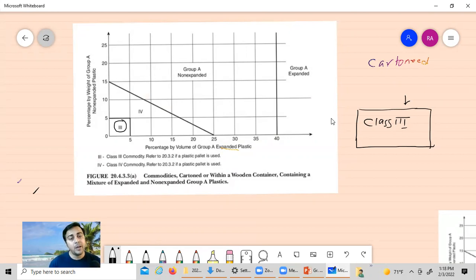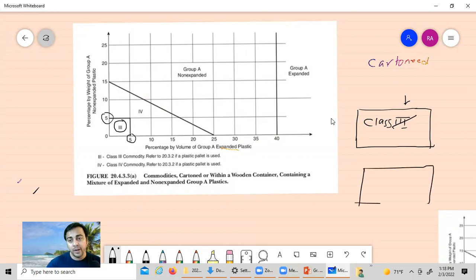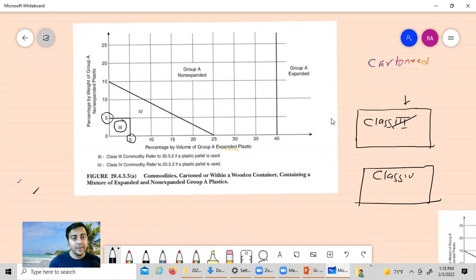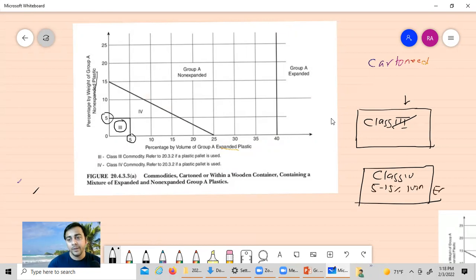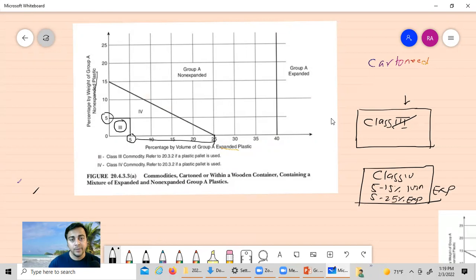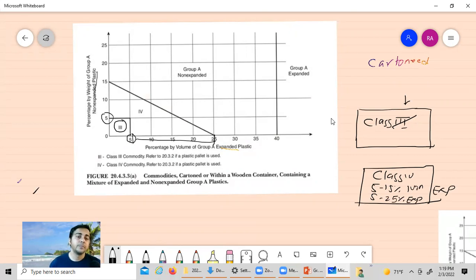If you go higher than 5%, it is no longer Class 3 — instead it becomes Class 4 commodities. In Class 4, anything higher than 5% up to 15% by weight of non-expanded plastic can be considered Class 4. So from 5% to 25% by volume of expanded plastic, as well as 5% to 15% by weight of Group A non-expanded plastic, or a mixture of both, can be classified as Class 4.